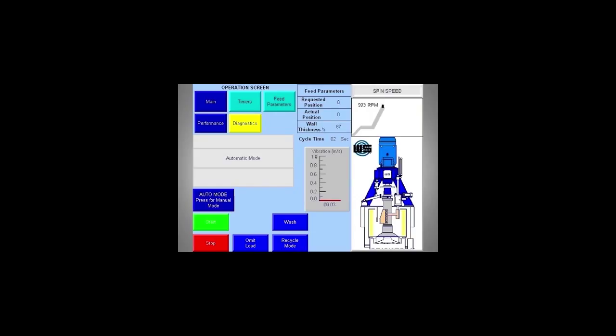Also, the red cycle stop button can be pressed on the operator station, which is just to the right of the HMI screen. If starting in manual mode, the load button must be pressed to begin loading the machine with massecuite. In either mode, manual or automatic, the omit load button can be pressed to stop loading by shutting the feed valve. Other options from this location are to operate in either sequence or recycle while in auto mode.